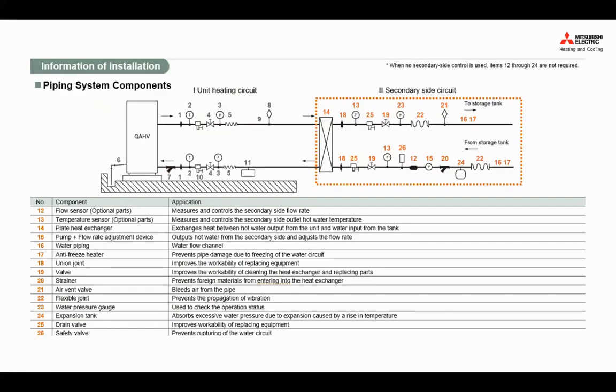So in here, again, this is taken from our design manual, just a sneak preview of what's upcoming. You can see most of the time, very basic, very similar compared to a conventional system. So you still need a strainer, you still need a flow sensor, you still need all that. You still need a valve, right? Temperature to read the temperature and all that, and then expansion tank, very similar. But keep in mind, the QAHV comes with its own internal pump.